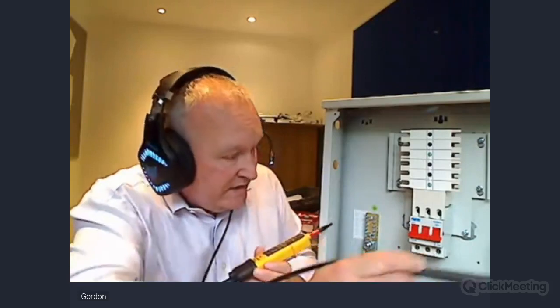So I like to test between earth and then L1, L2, L3 - that's 3 steps. Then I test between earth and neutral, which is step 4. Then between neutral and L1, L2, L3 - steps 5, 6, and 7. The only other steps then are between L1 and L2, L1 and L3, and L2 and L3.